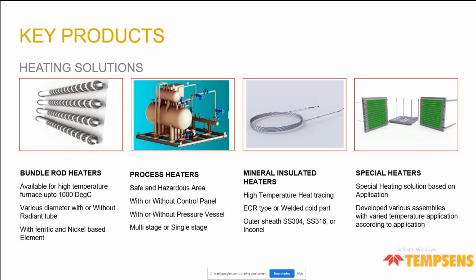Then we do bundle rod heaters - these are direct heating elements insulated by ceramic insulators, used up to 1000 degrees centigrade. They can come with an outside tube called a radiant tube, mostly used in non-ferrous industries like aluminium, and also in heat treatment furnaces and other areas.